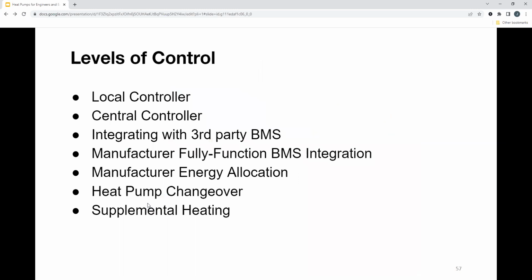All right, so I wanted to break this down into different levels of control we can do when we're installing heat pumps. So I'm going to mention local controls, central controller options, and integrating with third-party BMS. If there's an existing BMS already on site and you are doing a retrofit, how do we communicate to that? Manufacturer's fully functional BMS system, is that an option? And then manufacturer energy allocation, I'm going to talk about. This is really getting into the energy monitoring side, which is very beneficial as we progress towards the future. And then quickly talk about heat pump changeover, why this is important, and then mention supplemental heating and what you might need for that.